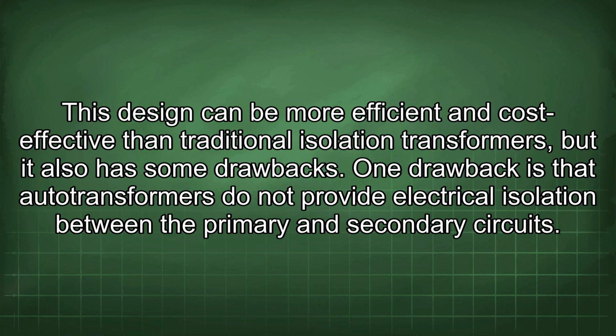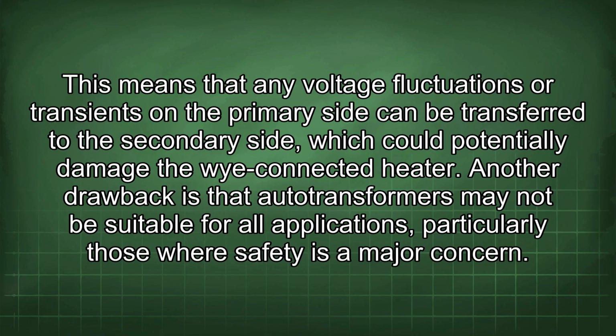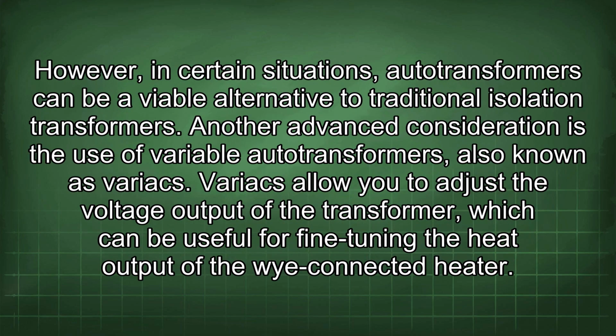One drawback is that autotransformers do not provide electrical isolation between the primary and secondary circuits. This means that any voltage fluctuations or transients on the primary side can be transferred to the secondary side, which could potentially damage the Y-connected heater. Another drawback is that autotransformers may not be suitable for all applications, particularly those where safety is a major concern. However, in certain situations, autotransformers can be a viable alternative to traditional isolation transformers.